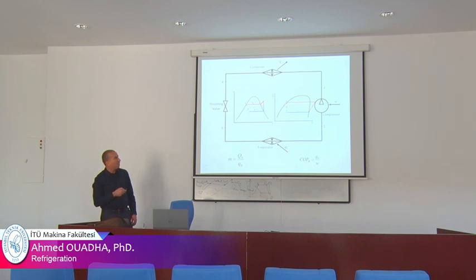The second one is to move point 4 here into the compressed liquid, because a commercial throttling valve requires to operate only with liquid, and also to increase the refrigeration effect. The refrigeration effect is H1 minus H5. So when we move this point here, we increase the refrigeration effect. Then we increase the coefficient of performance.